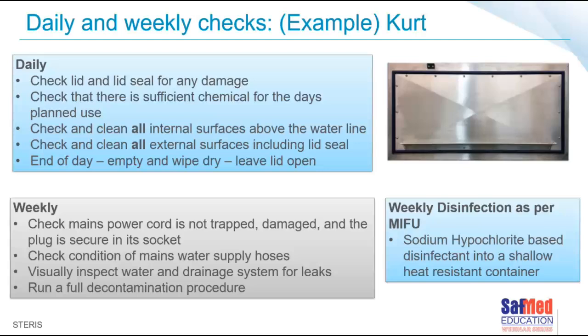So if it's above the waterline, that's above the fill line. Make sure it's clean, because remember when the lid is closed and you get the ultrasonics going, there's bubbles, it creates little aerosols, and it hits the top of the inner part of the lid. So please make sure you clean that, and then don't forget to clean the external surfaces, especially around the lid and the lid seal. That will prolong the lid seal and ensure that it closes correctly and the sensors work correctly on the lid. So that's at the end of the day. And at the end of the day, please empty the unit if it's a manual unit, wipe it and dry it correctly, and leave the lid open. As we mentioned, it's to prevent moisture buildup and bacteria growth during the night. And sometimes you get unpleasant smells when you open it up in the morning. It's from that bacteria growth.